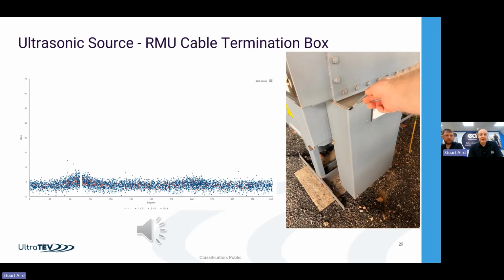Okay, another one is cable termination boxes. So this one is an RMU cable termination box, and my colleague has nicely used his pen to point exactly where he took the measurement from, right in that corner. We've got a little tiny air gap in the corner there that we're picking up this sound file through. Historically that's how you've got to take these measurements, and we managed to pick it up, so we can have a listen to it now.